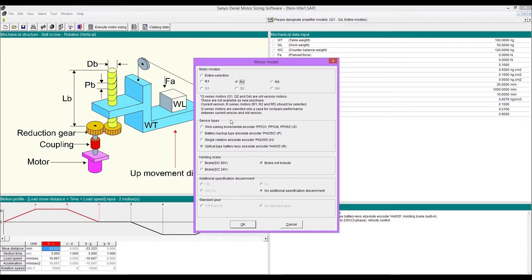Select holding brake model if needed. This time we selected a vertical motion, so we need a holding brake.